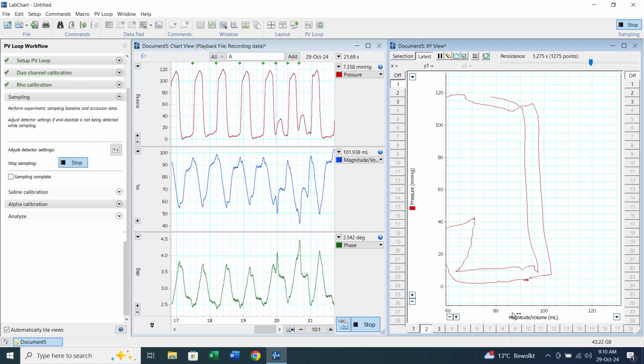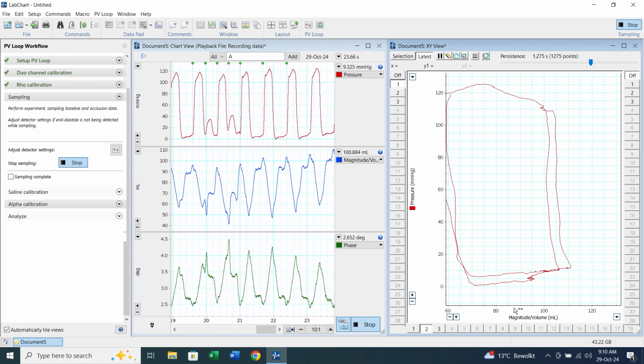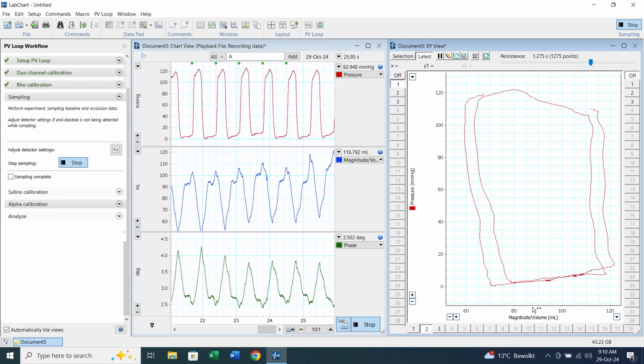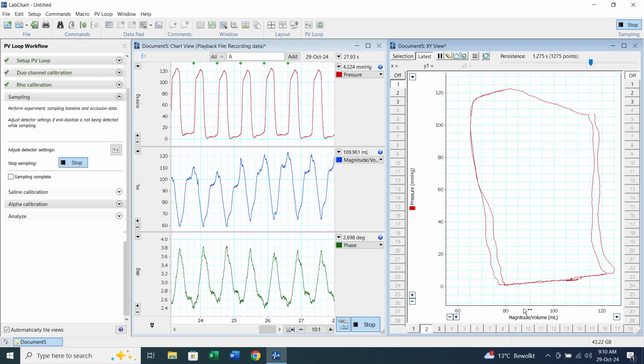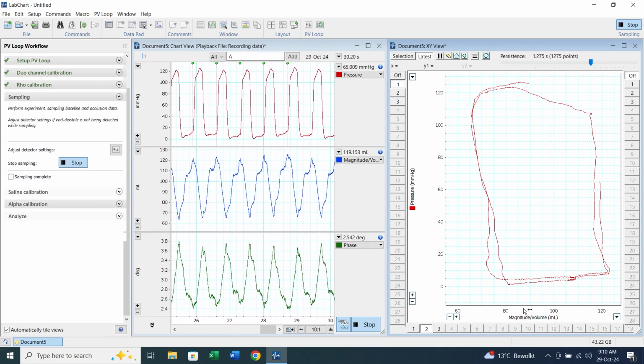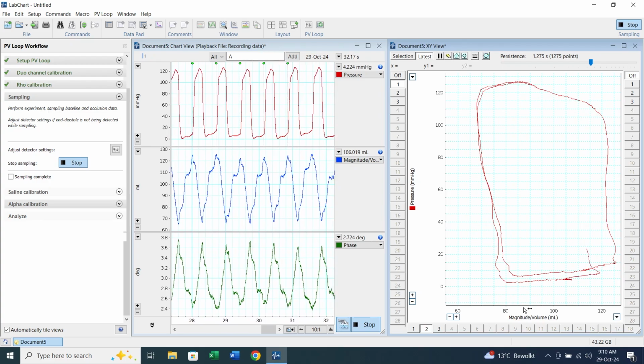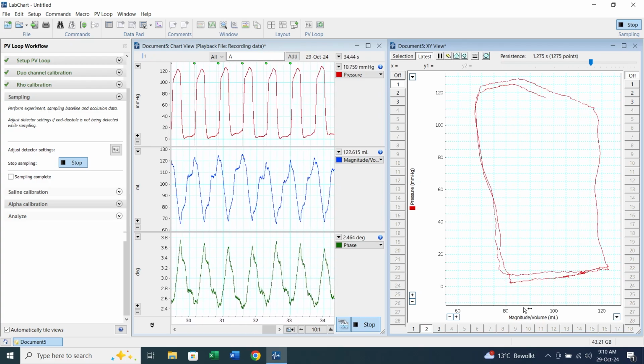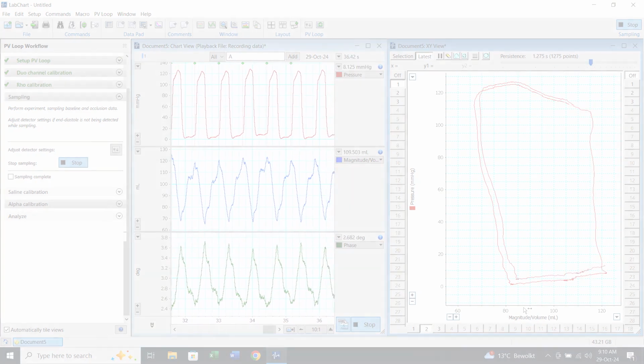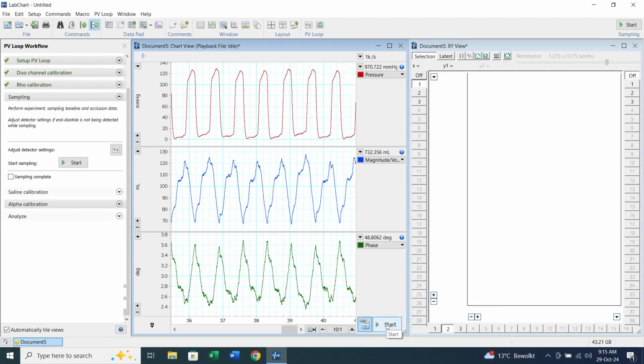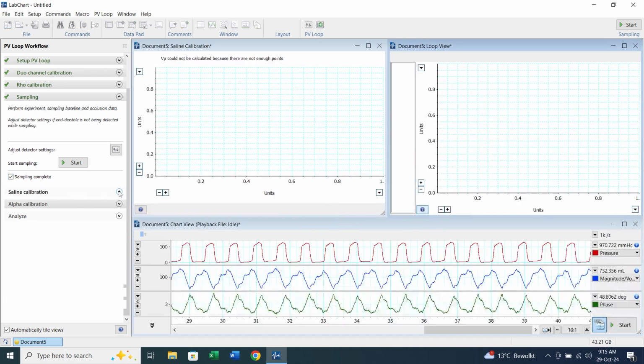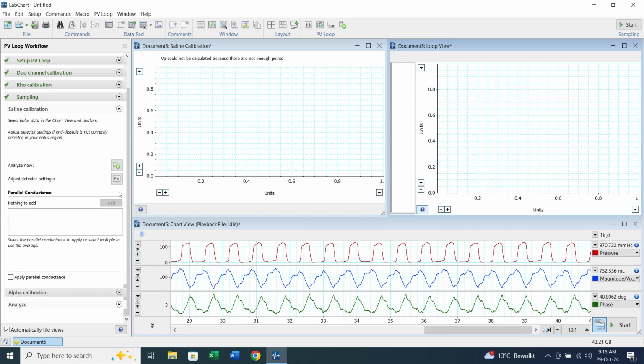Once the catheter position is optimal, with phase being within the specified ranges as shown in the manual, and volumes are plausible, the experiment protocol can be followed to record baseline, saline bolus for parallel conductance, and the occlusion data. Once the experiment has been completed, stop recording and check the box for sampling complete in the sampling section of the PV workflow. Now the parallel conductance can be calculated using the saline calibration section of the PV loop workflow.